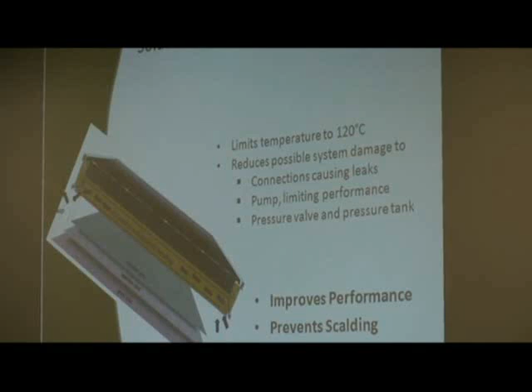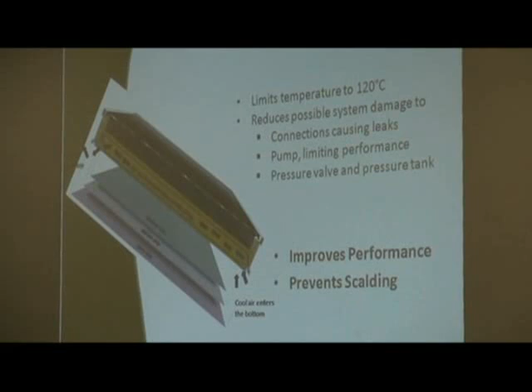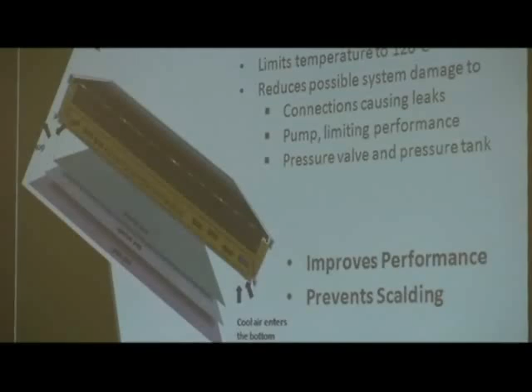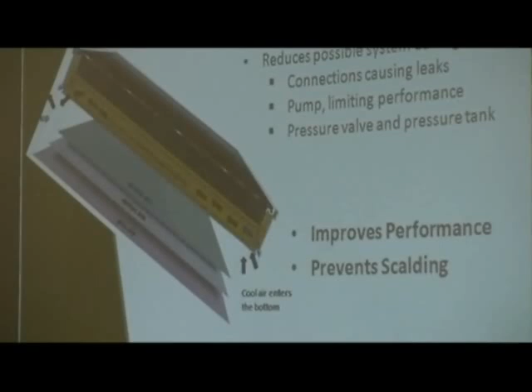This heat transfer fluid is stuck in that solar collector, and it is not displacing heat through potable water because there is no draw on the potable water. And the temperature within that solar collector will continue building. And what happens quite often in other systems is that they will eventually explode, or a pipe will burst, or something will happen and the system will fail. Usually it happens when you come home off of an 8-hour flight and it's 3 in the morning and you get home and there's hot water pouring all over your house.